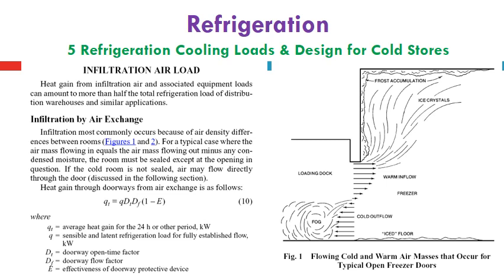Infiltration by air change or air exchange happens due to door opening at periodic times during the day, in the operating hours. Infiltration most commonly occurs because of air density differences between the rooms, as shown in figure 1 and figure 2. For the typical case where the air mass flowing in equals the air mass flowing out minus the condensed moisture, the room must be sealed except at the opening in question. If the cold room is not sealed, air may flow directly through the door, discussed in the following section.